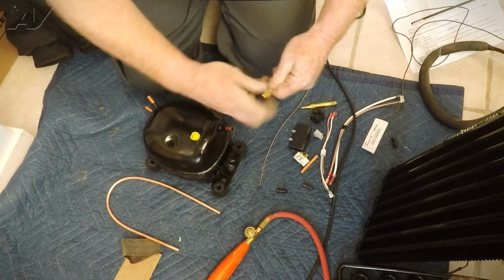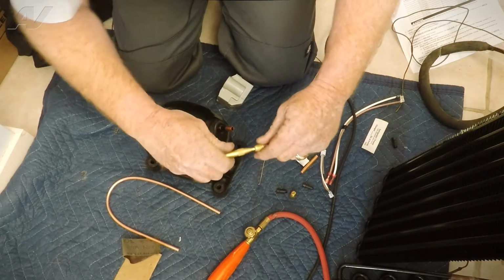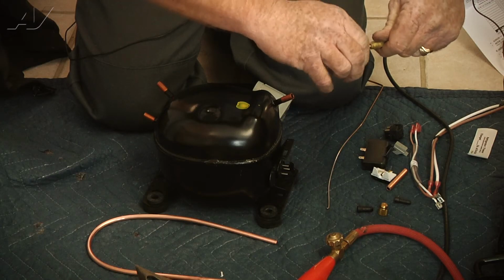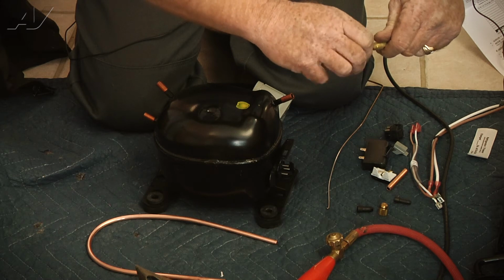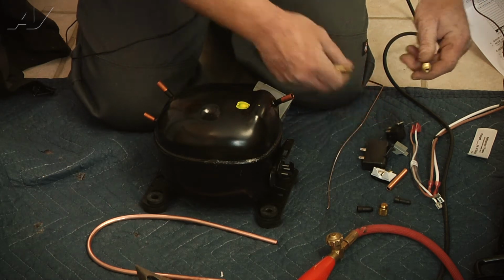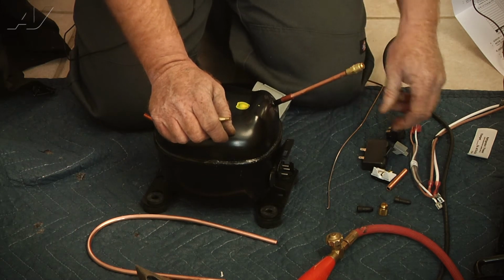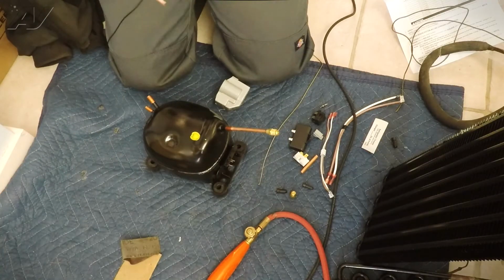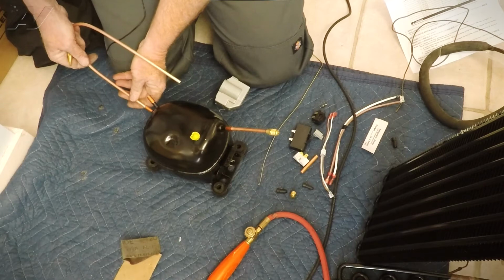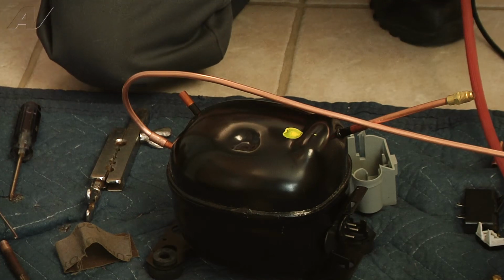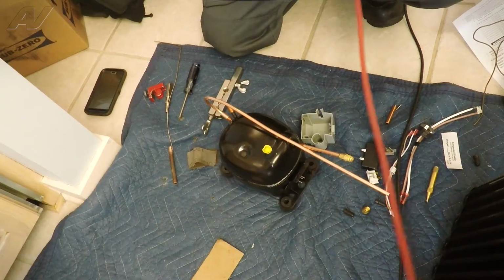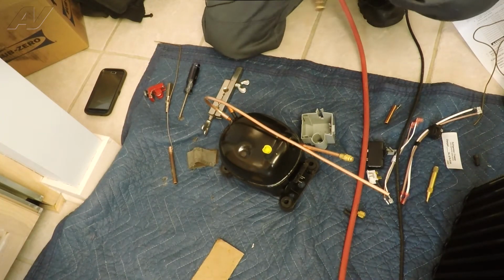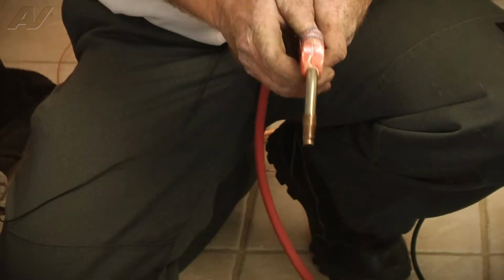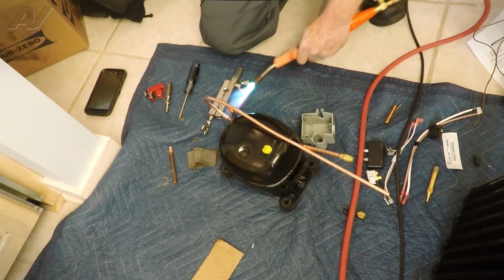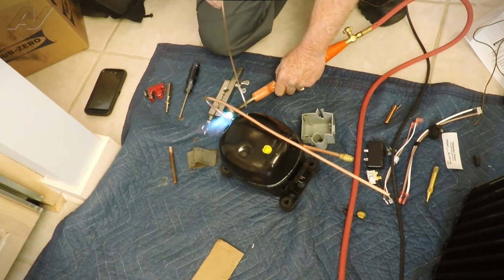We're going to take the access valve, remove the cap, and remove the Schrader core so that we don't damage the rubber seal on the Schrader core when we heat it up to braze it in place. And our tubing for the high side. Okay, so what I've done is I've made a coupler for the high side line. We're going to braze that into position. Start our torch. Get this side of the joint nice and hot.